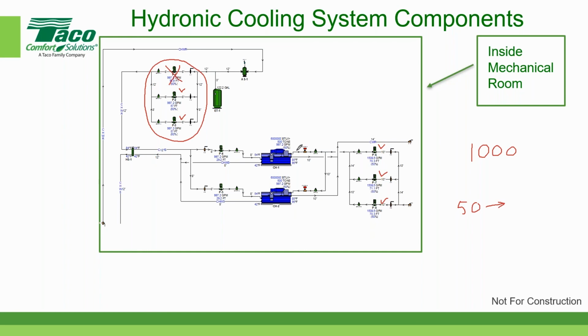So if you lose a chiller in a simple office building, for the most part, most people are not going to notice for the majority of hours. Now, obviously, if you get into a peak cooling day, you're going to seriously miss that chiller. But in a simple office building, it's usually economical to do it that way. Some people for simple office buildings will put in two chillers like I did the pumps and make them 50% each. But it's a big piece of equipment. It's very expensive. Chillers are relatively reliable, especially centrifugal chillers today. They're built to industrial standards.